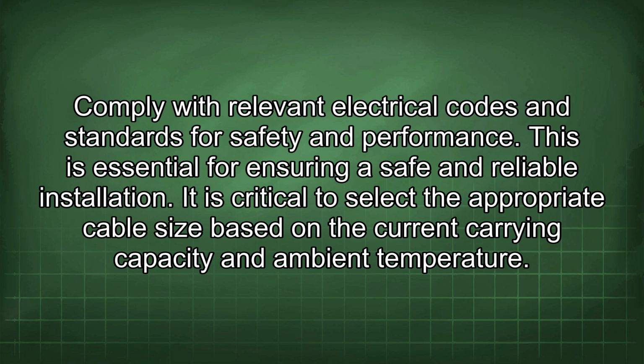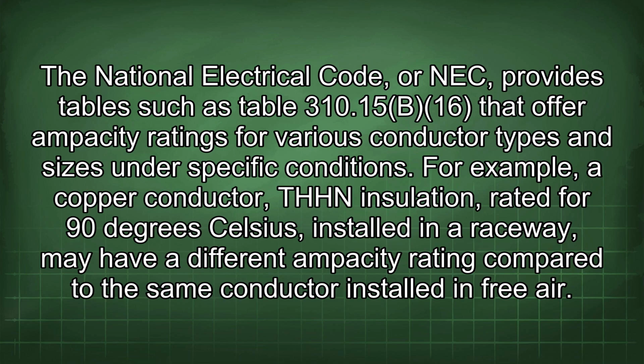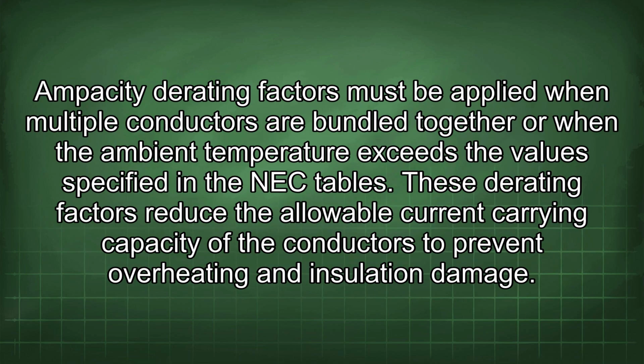It is critical to select the appropriate cable size based on the current carrying capacity and ambient temperature. The National Electrical Code, or NEC, provides tables such as Table 310.15(B)(16) that offer ampacity ratings for various conductor types and sizes under specific conditions. For example, a copper conductor with THHN insulation rated for 90 degrees Celsius installed in a raceway may have a different ampacity rating compared to the same conductor installed in free air. Ampacity derating factors must be applied when multiple conductors are bundled together or when the ambient temperature exceeds the values specified in the NEC tables. These derating factors reduce the allowable current carrying capacity of the conductors to prevent overheating and insulation damage.